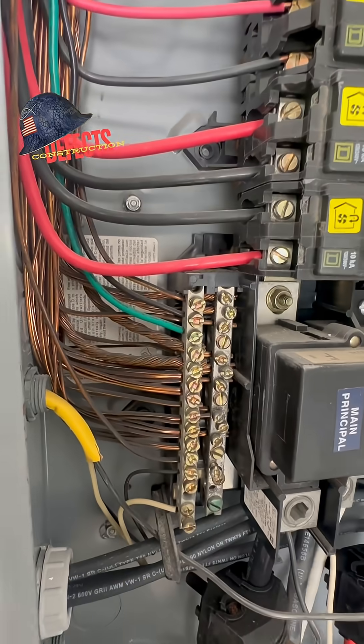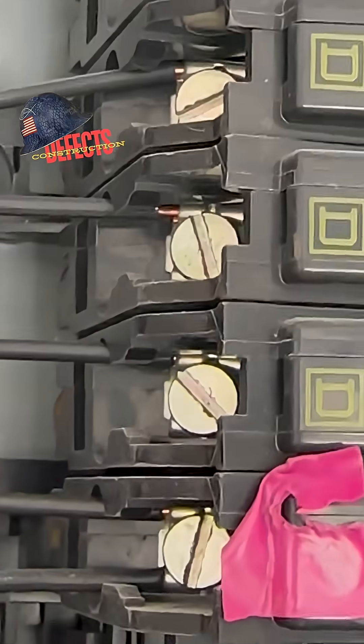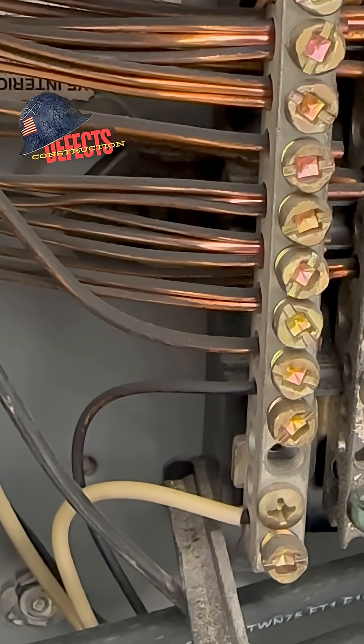It's not something that's affecting all the wiring. If you look at the hot wires, see how shiny copper they are? Generally, Chinese drywall affects everything. So I think that this is a grounding issue.